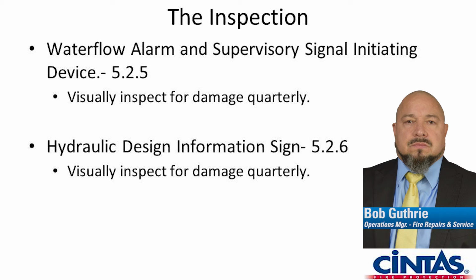Flow supervisory signal initiation. This is something that is inspected quarterly for damage. It's also on a semi-annual inspection. We actually test these. So quarterly, we'll look for damage to the switch, whether it be a flow switch or a tamper switch on an OS&Y valve. And then semi-annually, we're doing a test on it to make sure it actually functions. Hydraulic design information sign. We look for that on a quarterly basis.